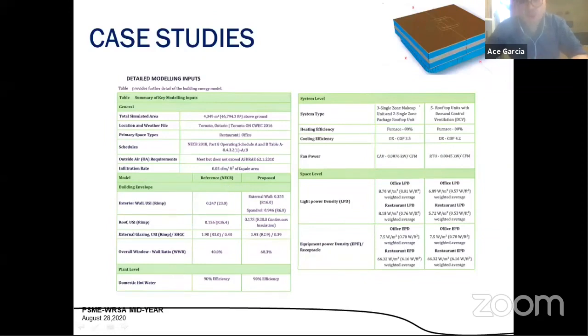It's located in Toronto, and the NECB is our National Energy Code for Buildings, like ASHRAE or LEED standards here in Canada. It specifies the architectural thermal performance and the proposed mechanical system, similar to ASHRAE 90.1, where your proposed building design determines the baseline energy system. Since we have an RTU, the baseline selection is a makeup air unit with an RTU as well.